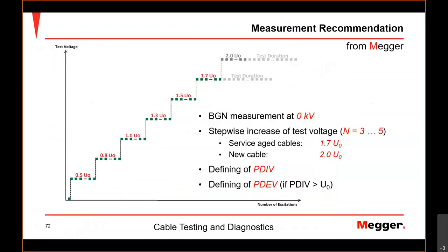And the whole process of your measurement would be, after your calibration, you do your first measurement. That's at 0 kV. That's your noise level. You do a measurement, and your coupler, this orange one with the two tubes there, will detect everything that's there at 0 kV. You apply nothing. So everything that's coming into the instrument must be coming from ambient noise. You know the noise level, then that's okay.